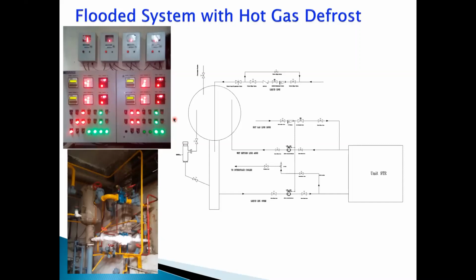So what is the alternative? The best alternative available is to use hot gas. As we all know, in our refrigeration system the discharge of the compressor is very hot. The gas goes to the condenser, and water or air is used to chill it and make it a liquid. So some part of the gas can be brought into the evaporator by an automatic system, closing the liquid feed and putting in the hot gas.